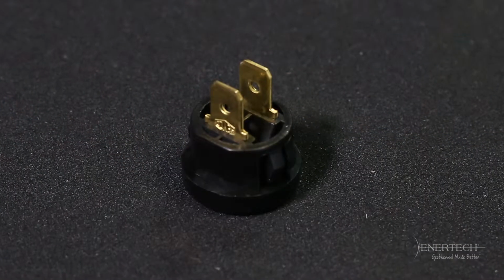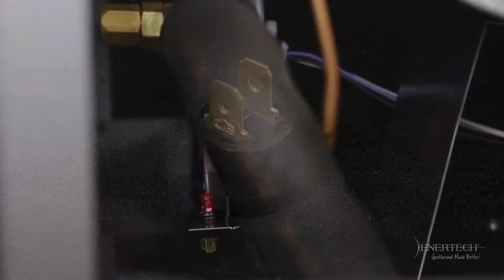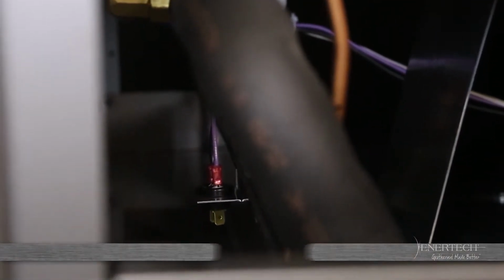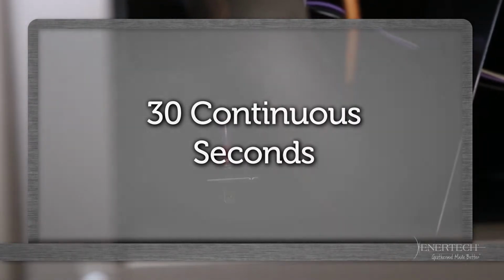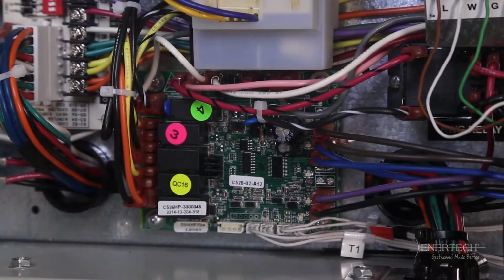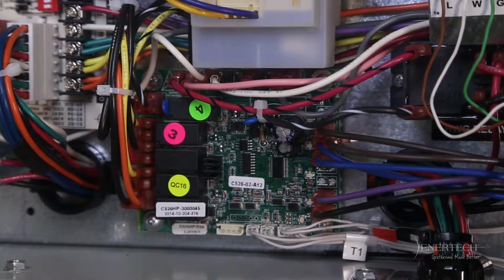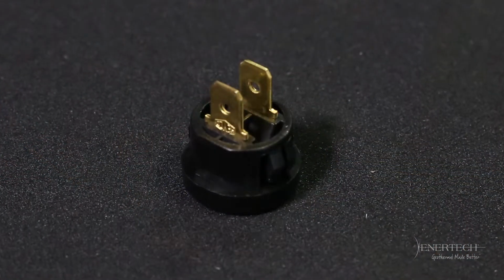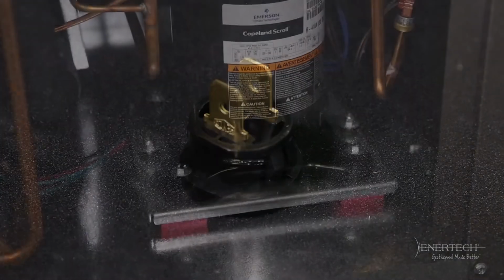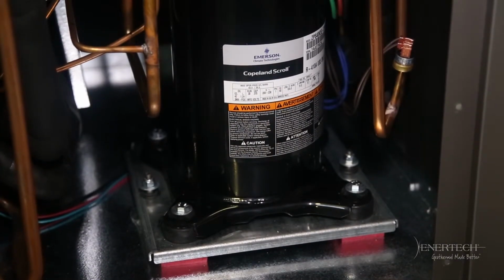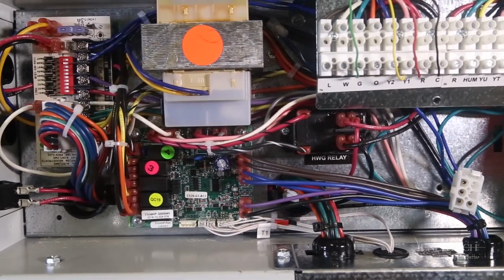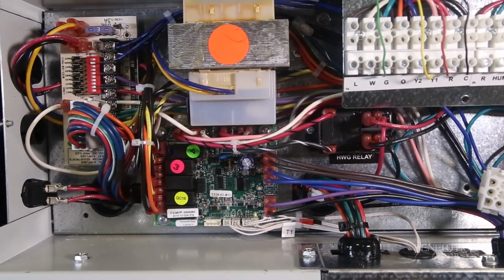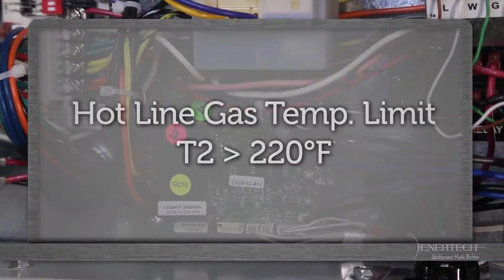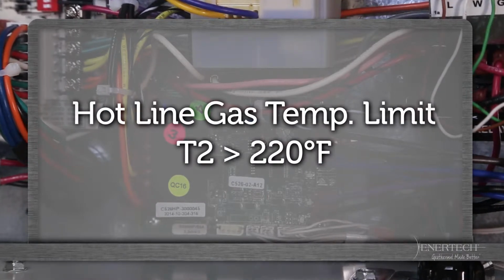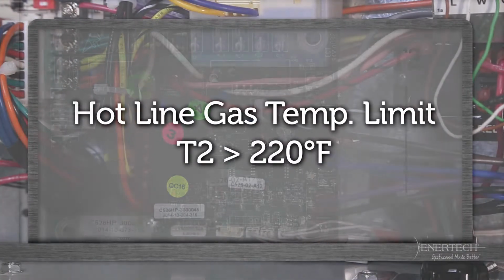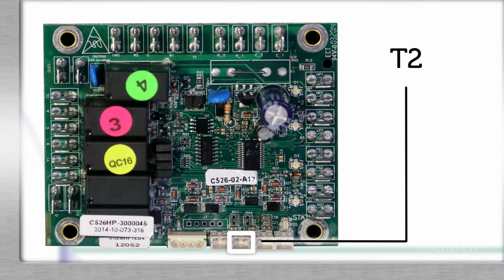The control board utilizes an impedance sensing liquid sensor at the top of the drain pan. When water touches the sensor for 30 continuous seconds, the sensor sends a ground signal to the lockout board indicating a condensate overflow fault has occurred. If water touches the condensate overflow sensor for 30 continuous seconds, the compressor operation will be interrupted. The control will go into a fault retry mode. There is no delay of switch monitoring at startup. When T2 is greater than 220 degrees for 30 continuous seconds, compressor operation will be interrupted. The control will go into fault retry mode.